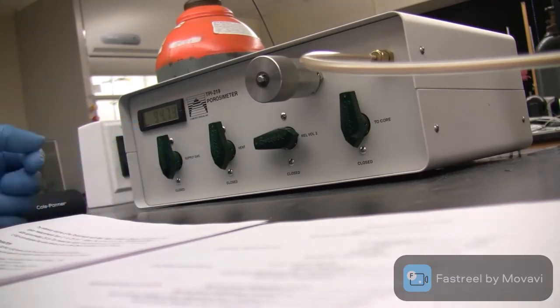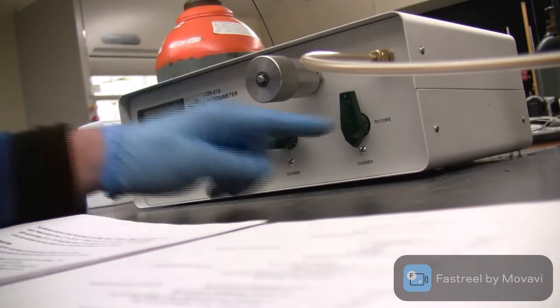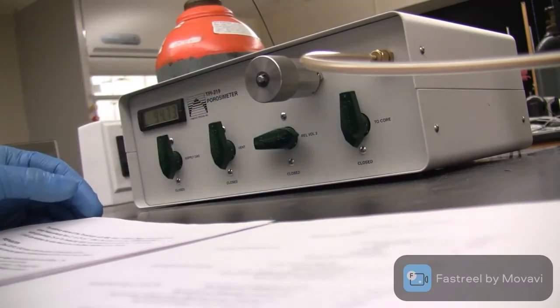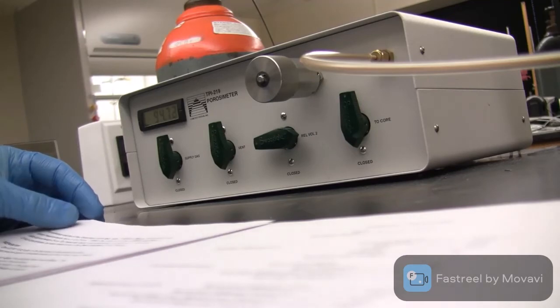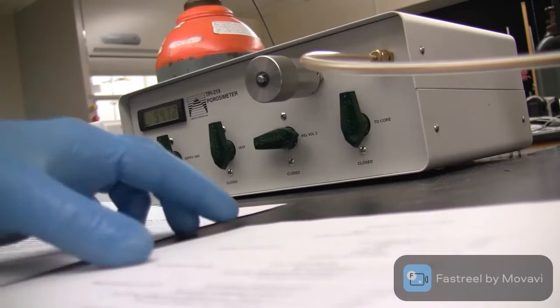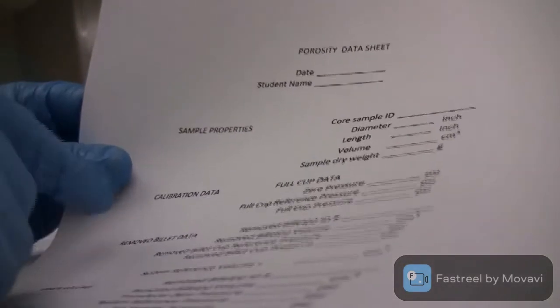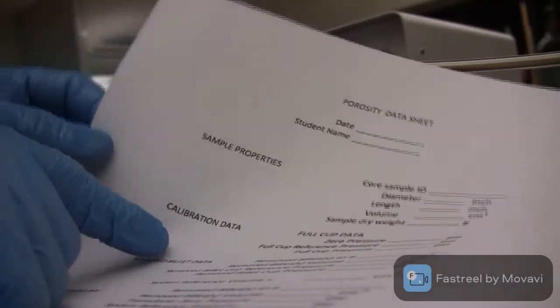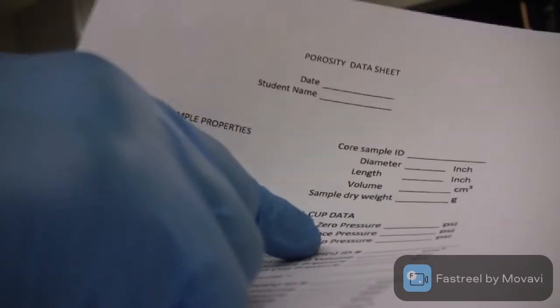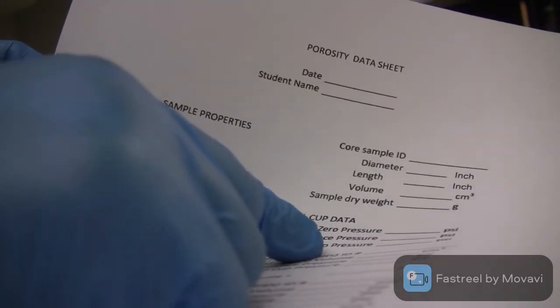It should be enough. Let's close it, wait for 10 more seconds, and then we open the vent and the to core valves, and we record the pressure in the full cup data section in your data sheet.